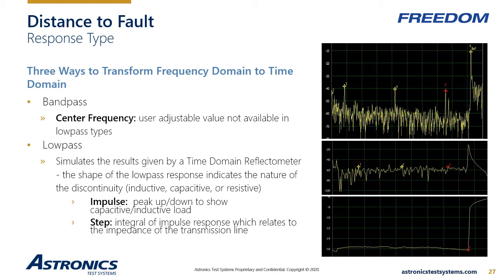Low-pass processing presents the data in a way that relates more closely to what you would see with a TDR. The user selects either impulse or step response based on the need or preference. The impulse view peaks up and down based on the capacitive or inductive nature of the fault. The step response is the integral of the impulse response and relates to the impedance of the cable. The trace will rise or fall based on the impedance of each cable segment. With experience, the user will learn which response type best suits each situation. As with the previous tools, measurement accuracy and speed must be balanced to meet the needs of the situation.